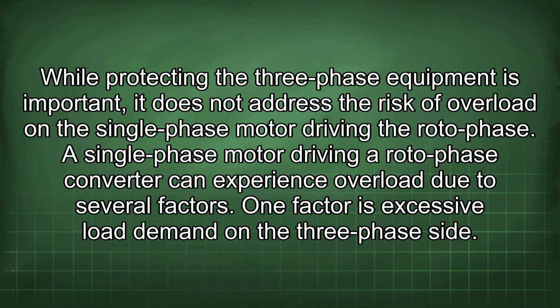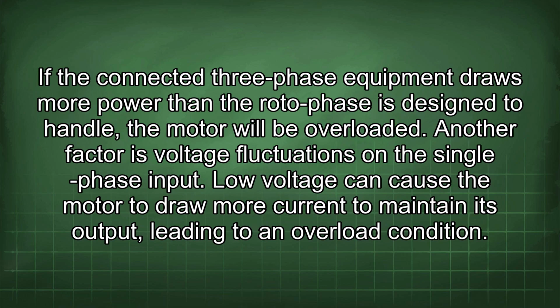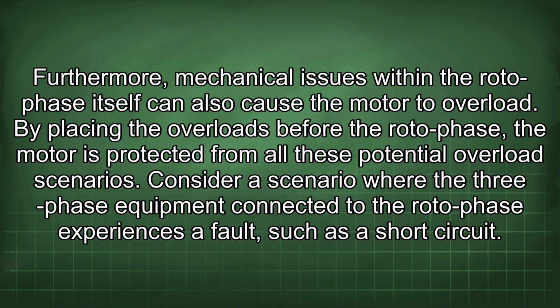One factor is excessive load demand on the three-phase side. If the connected three-phase equipment draws more power than the roto-phase is designed to handle, the motor will be overloaded. Another factor is voltage fluctuations on the single-phase input. Low voltage can cause the motor to draw more current to maintain its output, leading to an overload condition. Furthermore, mechanical issues within the roto-phase itself can also cause the motor to overload. By placing the overloads before the roto-phase, the motor is protected from all these potential overload scenarios.